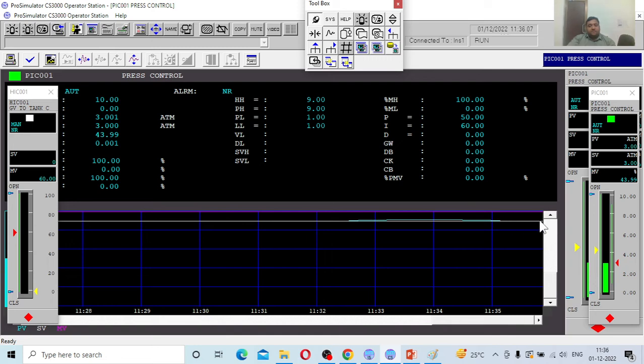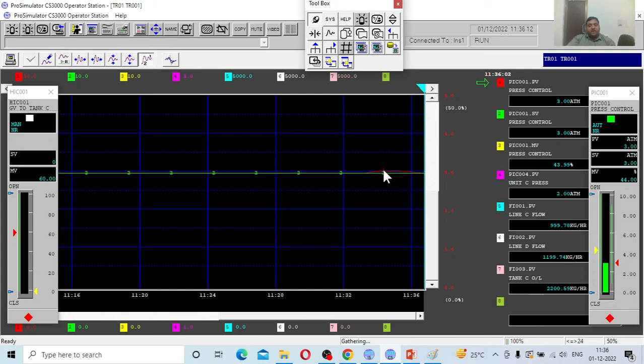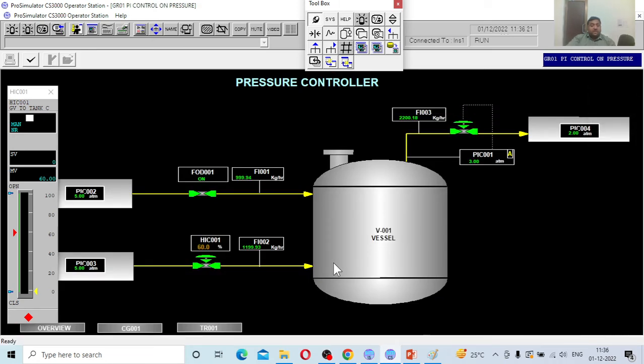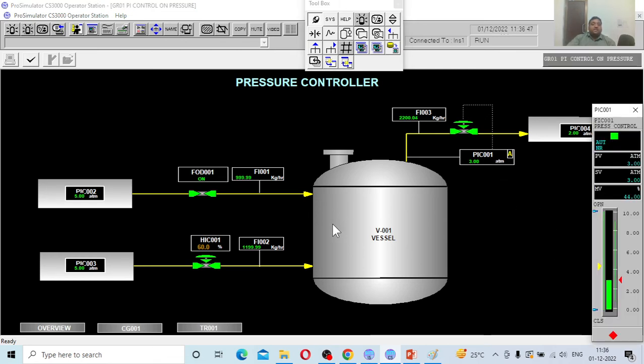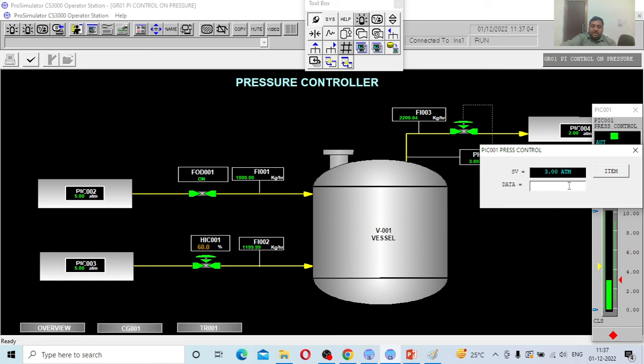Now in the trend window, both lines are getting matched — there was a small hump earlier, but now the process value and set value are matched. This first scenario is called the regulatory problem, also known as the disturbance problem — a disturbance was created and the controller took action to reduce it. The second thing we discuss is called the servo problem, which means changing the set point. I am now going to change the set point from 3 atmospheres to 4 atmospheres.